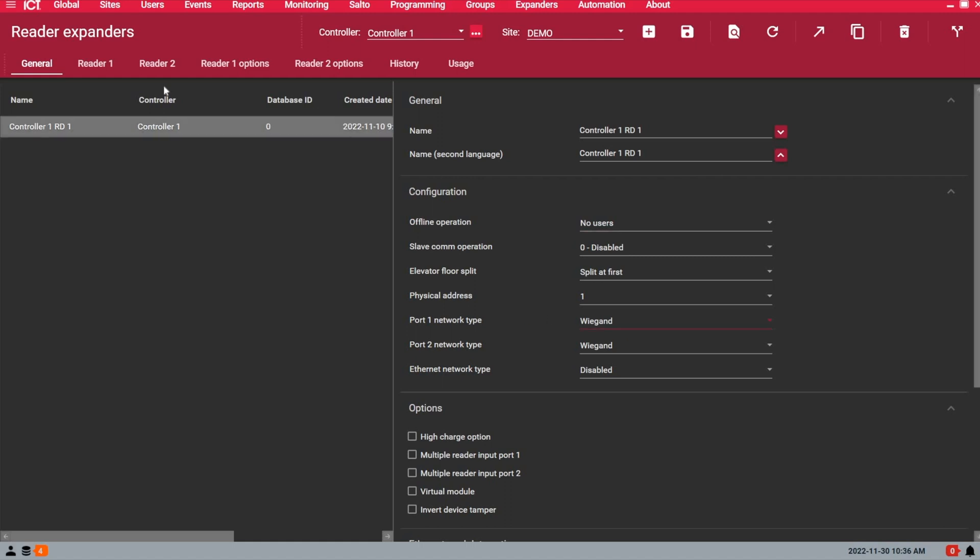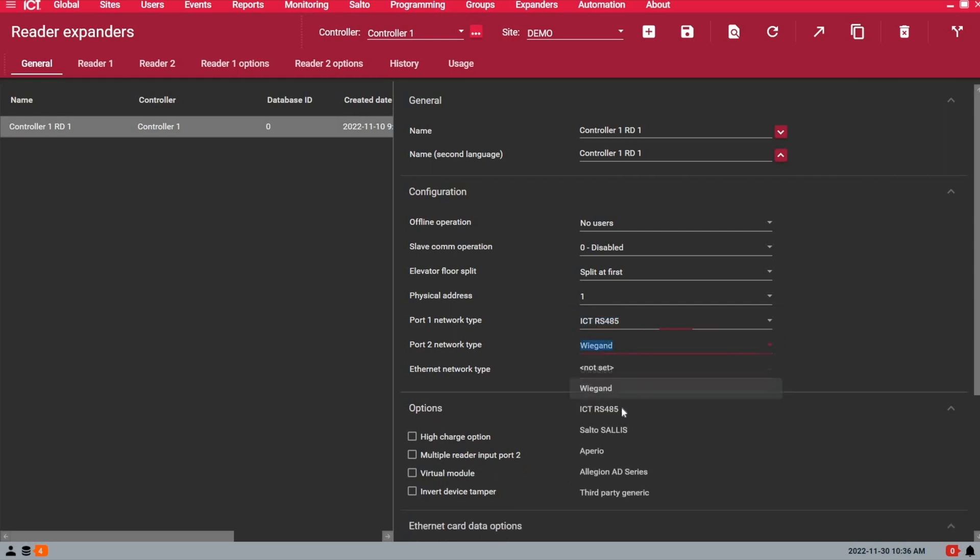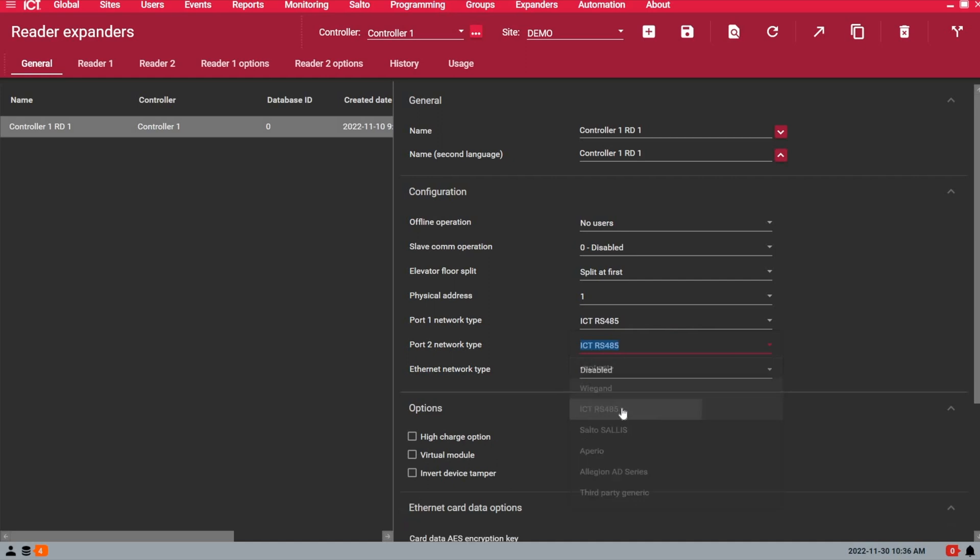If you have reader expander 1 created, what you want to do now under the general tab, make sure that the port 1 network type is set to ICT-485, the same for port 2. So on the demo kit here, we have port 1, we have port 2, and this is what we want to enable and use. I'm going to save it.